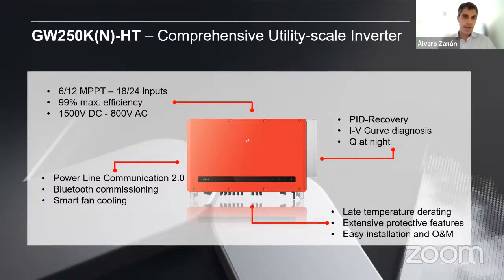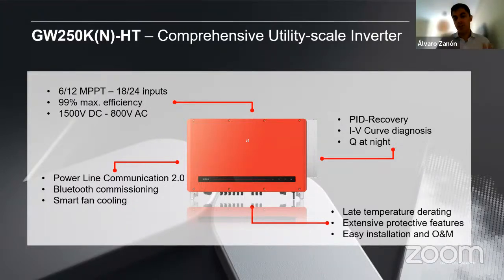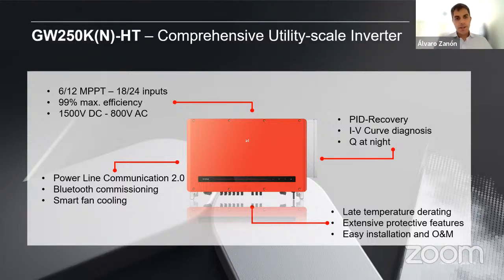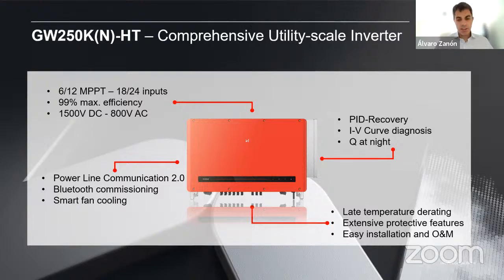Our inverters have very high conversion efficiency and importantly a very high dynamic MPPT efficiency of 99.8–99.9%, representing how fast the MPPT algorithm finds the operating point after a disturbance such as a passing cloud — this greatly impacts energy yield. Our inverters work at 1500V DC, 800V AC, which is standard for string inverters. Very important for CAPEX and O&M is power line communications (PLC), which transmits monitoring and control data directly through the AC power cables — no extra monitoring cable needed.